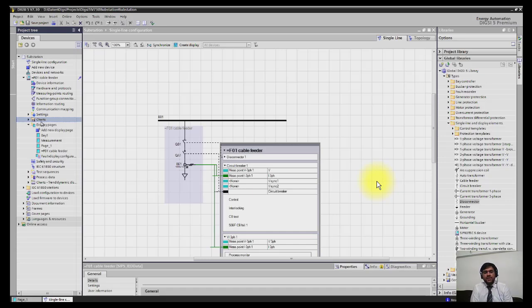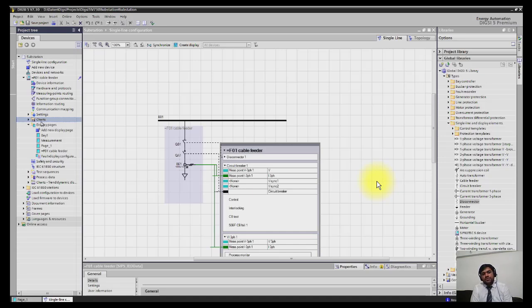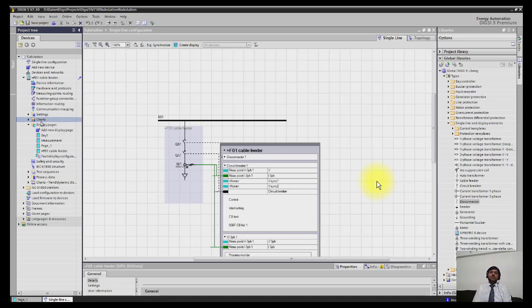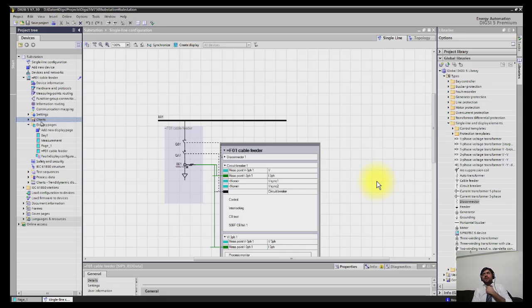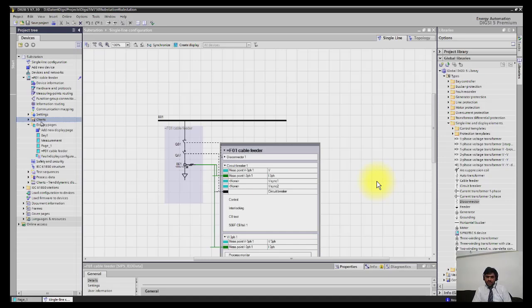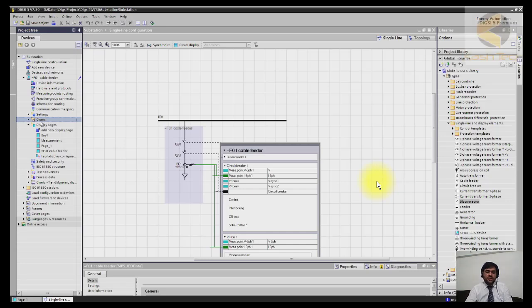Only breaker could be operated open or close irrespective of isolator status, but if the isolator status is intermediate, in that case breaker should not operate. Similarly, the isolator should be able to be operated only if the breaker is open, and if it is closed the isolator should not operate, or also if the breaker status is not clear or intermediate it should also not operate.